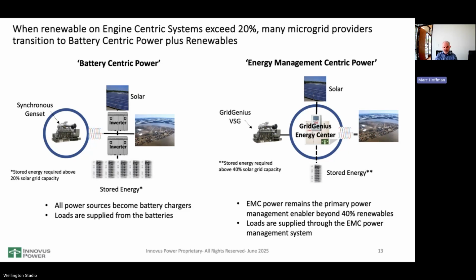Generally speaking, the synchronous gensets are inefficient once you drop below, say, 70 or 60% load. With natural gas, they drop off a table even earlier than that. So what they basically have to do is say, all right, if we're going to use the genset as a battery charger, we're going to run it at high loads, turn it on, run it out at full load, and the sizing of the battery bank is really determined by how often you want to turn the genset on and off during the day to recharge the batteries.